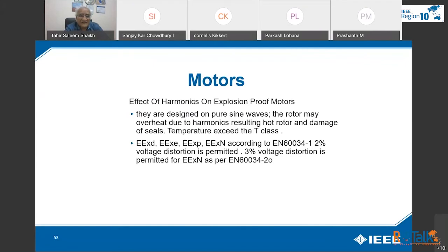EExd, EExe, EExp, EExN, according to EN 60034, 2% voltage distortion is permitted. 3% voltage distortion is permitted for EExN as per EN60034-20. So you have to be very careful when you are using your equipment in explosive atmosphere. The environment will have too much effect on these components.